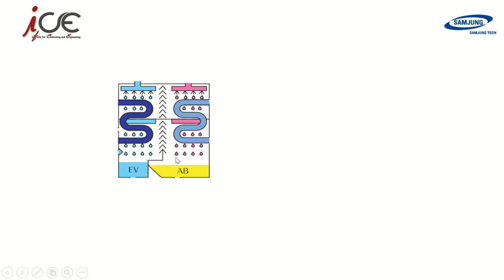The second part, located on the right side, is the absorber, which consists of a large bundle of copper pipes. Inside the absorber, concentrated lithium bromide absorbs the water vapor generated in the evaporator. So lithium bromide in this case is the absorbent — that is why this part is called the absorber.